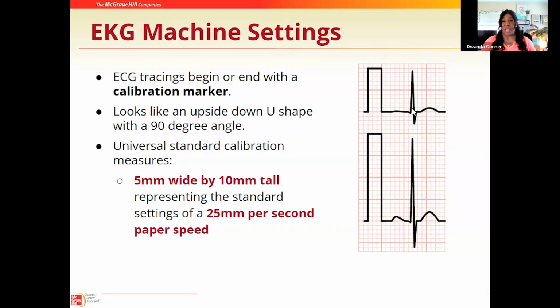You can see here that the gain or amplitude will change if the calibration marker is not as it should be. So our universal standard calibration measures would be 5 millimeters wide by 10 millimeters tall. This is representing the standard settings of a 25 millimeter per second paper speed. 5 millimeters wide by 10 millimeters tall. Settings of a 25 millimeter per second paper speed, which is standard for calibration of an EKG.